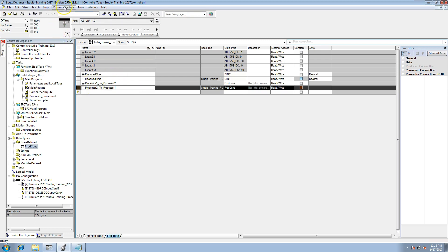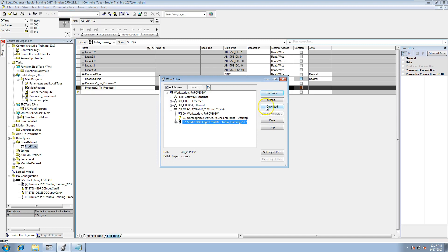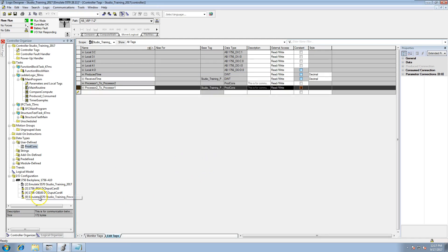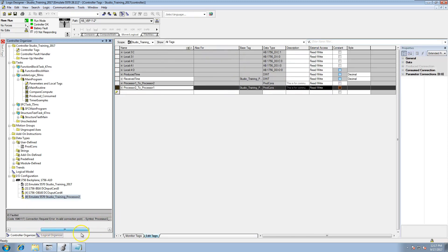Now that we have those set up, it's easy to tell who's who. We'll go ahead and download both processors. I'll show you something: if it's not properly lined up you'll get a triangle warning. I don't have anything downloaded to Processor 2 right now — notice the triangle on Processor 2 down here. If I click it, it will tell me where the problem is.